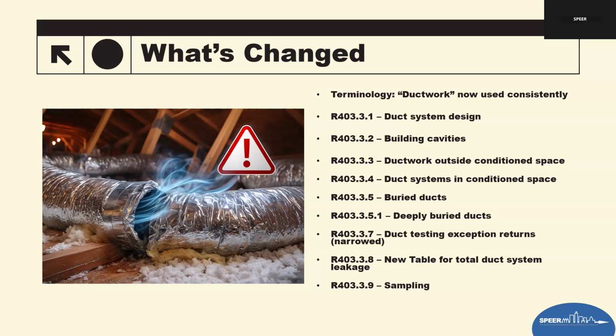I'm going to mention this real quick because I still see some mention of this happening around Texas. There's total duct leakage, known as TDL, and there's leakage to outside, also known as LTO. We'll talk about what those mean a little bit later, and why the LTO is no longer allowed by code. The one big thing now is R403.3.9, sampling for multifamily.